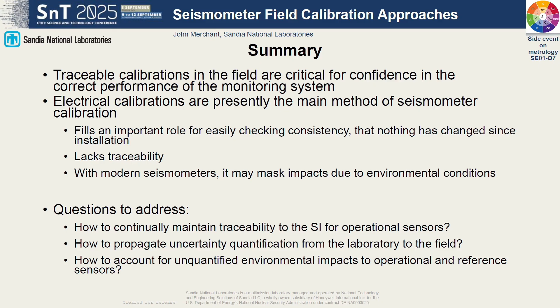So with that, my table of points: I'm not arguing against performing electrical calibrations. I think they're a useful tool. From time of installation, they can give you an indication, a state of health indicator, that likely things haven't changed, but they're an incomplete tool. And something more is needed to fill that gap, to be able to tell what the environmental susceptibility effects are for the measurements the instruments are making, that has traceability. It's necessary but not sufficient.